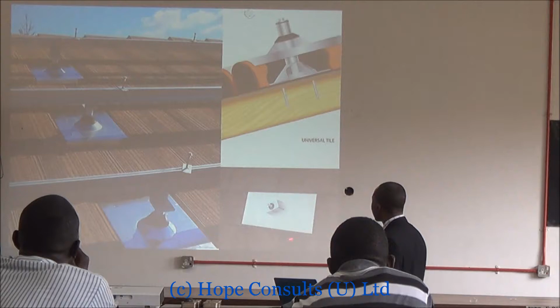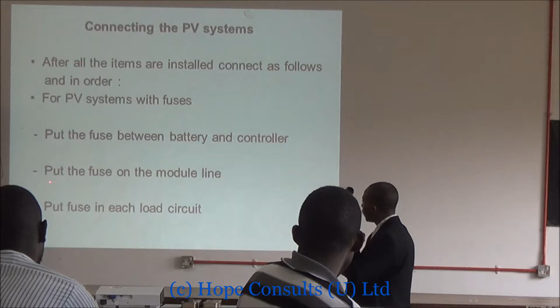So after all the items are installed, you connect as follows. In PV systems, you have to have fuses. You have to put a fuse between the battery and the controller. So between your controller and the battery, you need a fuse there. The charge controller controls the amount of charge, but in case anything happens, make sure that you have a fuse in between.